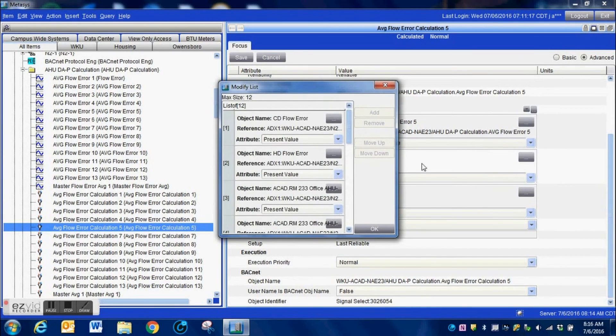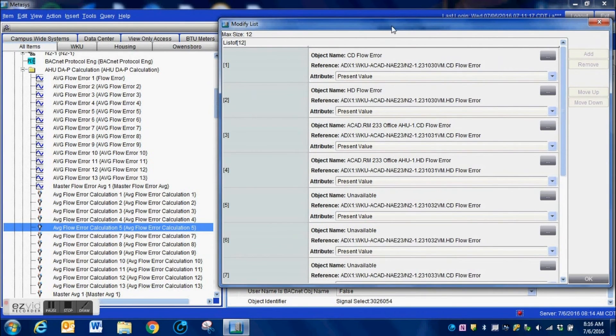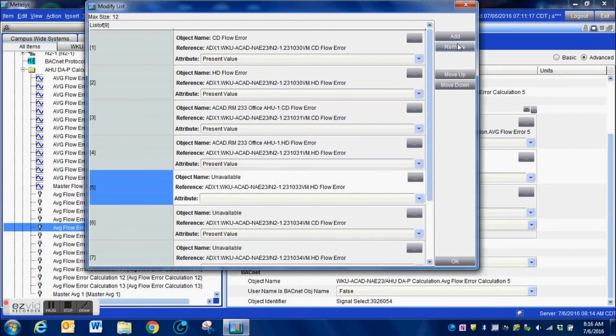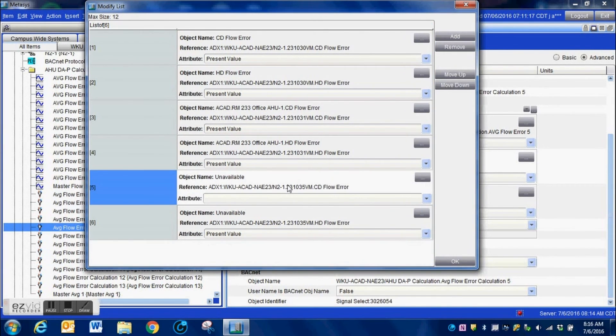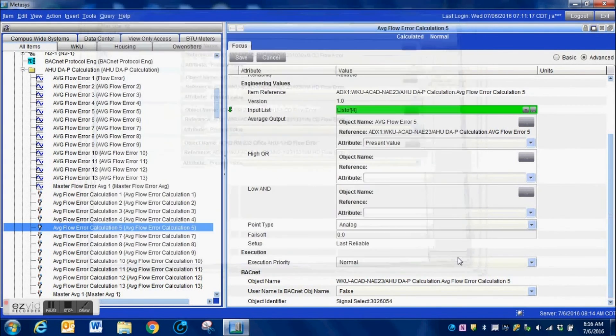Get that number all the way down to zero. I know it's easy to think "we've got it close, let's stop" — don't do that. Go all the way through every bit of that logic and get every one of them out. You can see here on one of my slave lists for this logic block I've got some points that are unreliable — again, part of those controllers that were removed. I'm simply going through and removing each one until every one of them is gone.